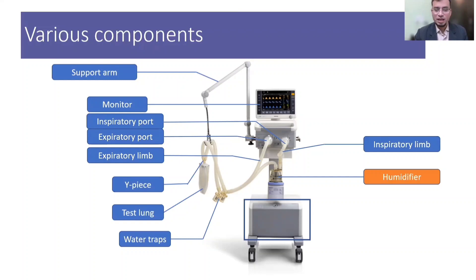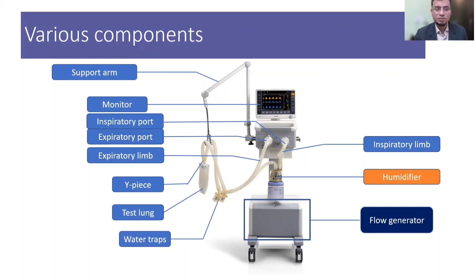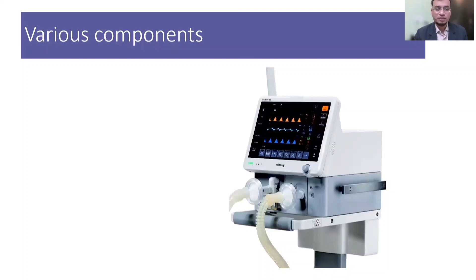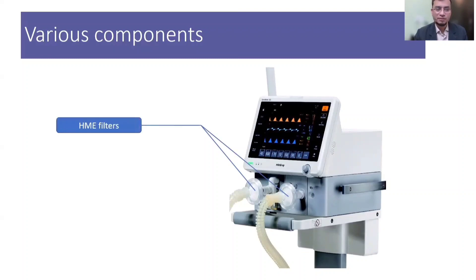Every ventilator has a flow generator unit inside which generates the inspiratory flow. This unit is driven by electricity and also has a built-in backup battery. To prevent cross-contamination and to conserve the heat and moisture of the patient's respiratory system, HME filters are connected to the inspiratory and expiratory ports.